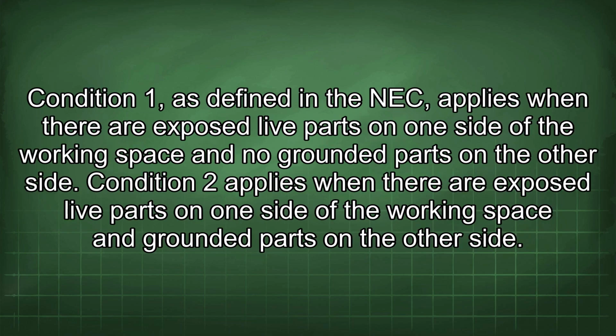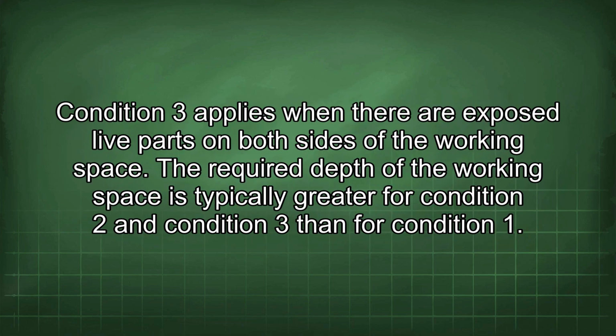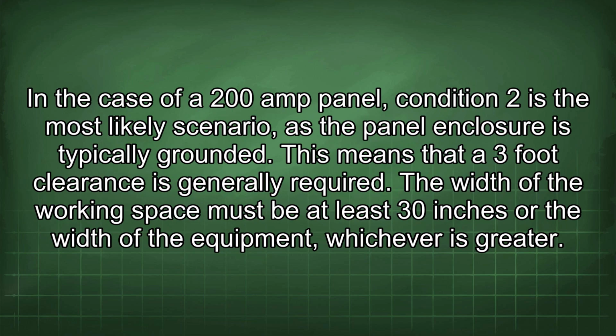Condition 1, as defined in the NEC, applies when there are exposed live parts on one side of the working space and no grounded parts on the other side. Condition 2 applies when there are exposed live parts on one side of the working space and grounded parts on the other side. Condition 3 applies when there are exposed live parts on both sides of the working space. The required depth of the working space is typically greater for Condition 2 and Condition 3 than for Condition 1. In the case of a 200 amp panel, Condition 2 is the most likely scenario as the panel enclosure is typically grounded. This means that a 3-foot clearance is generally required.